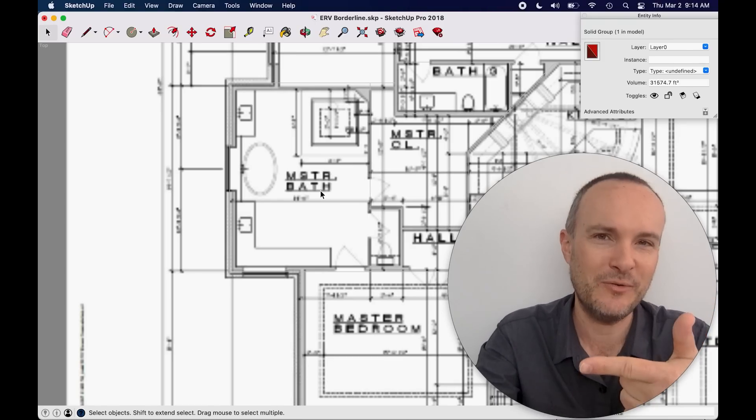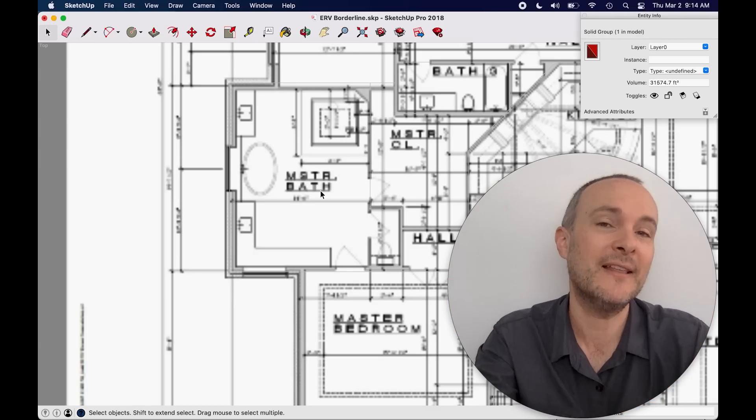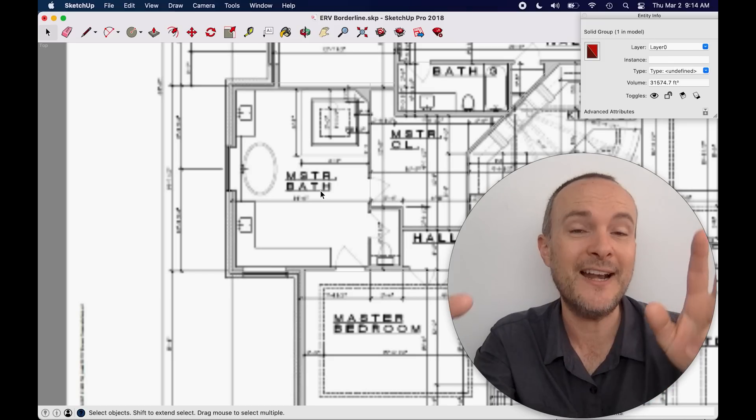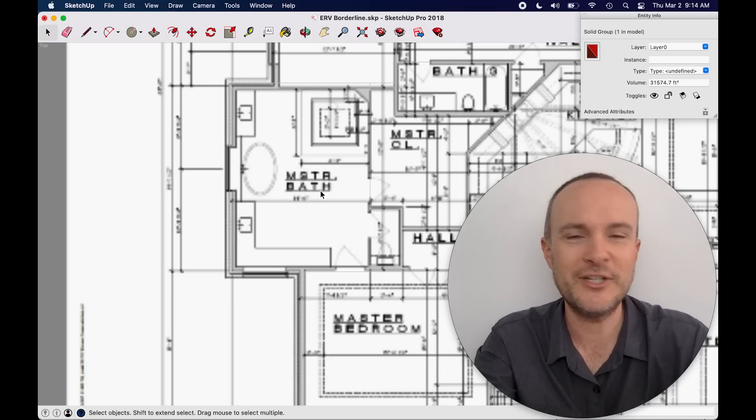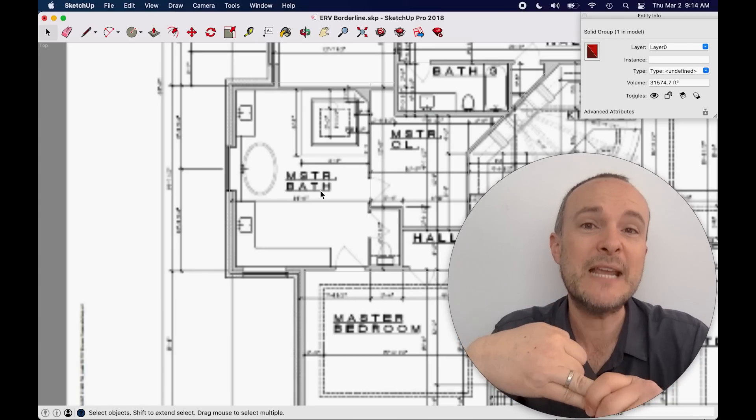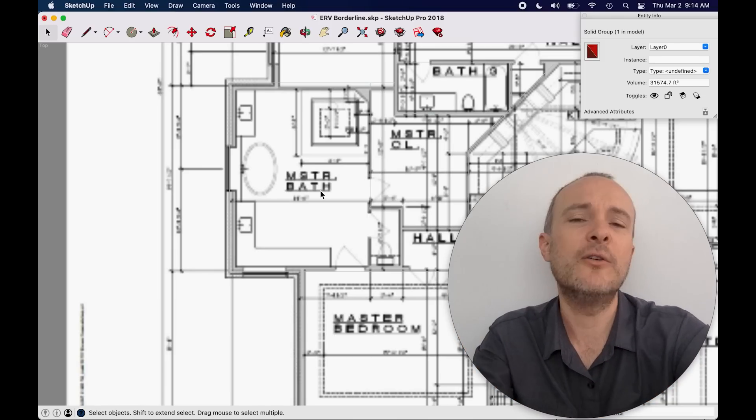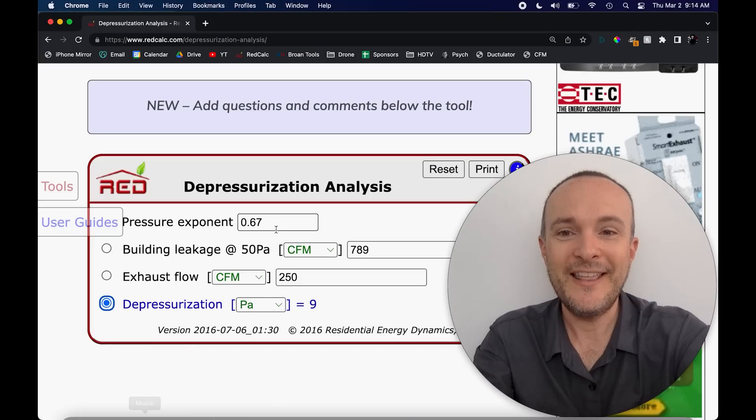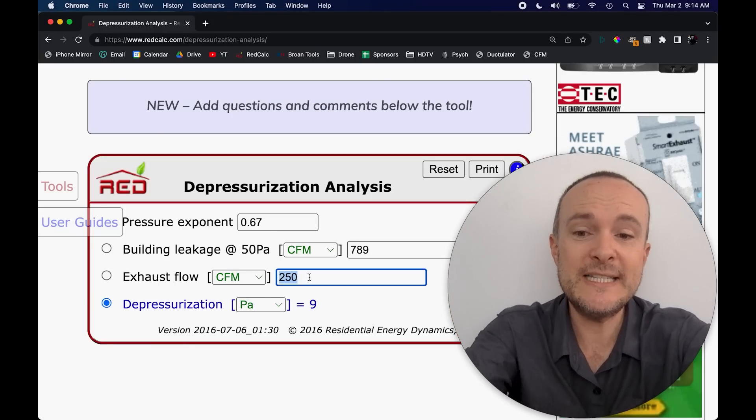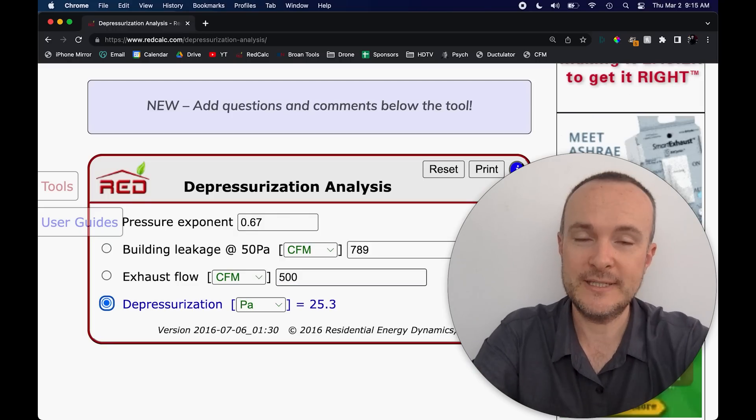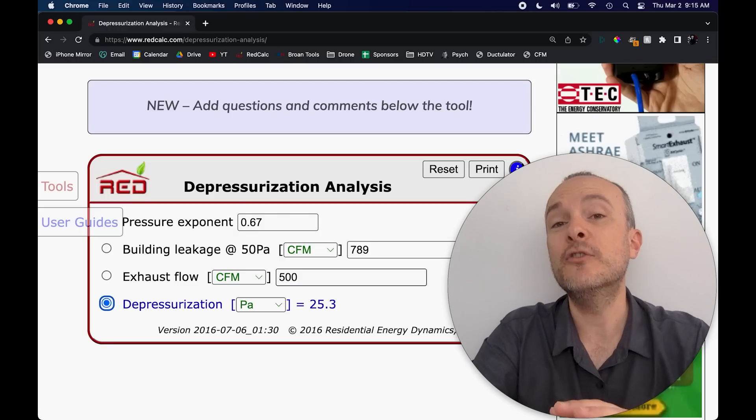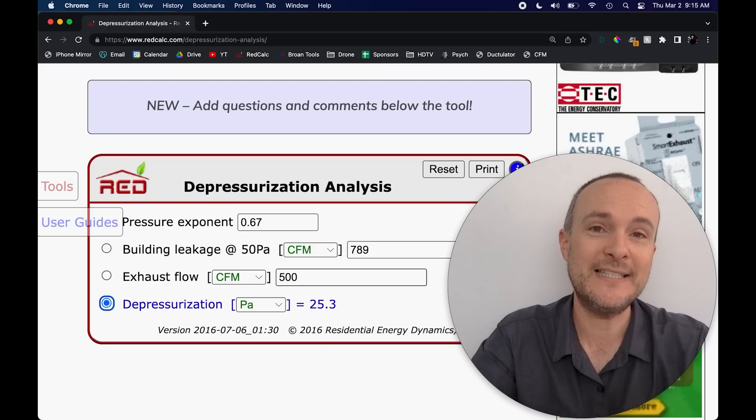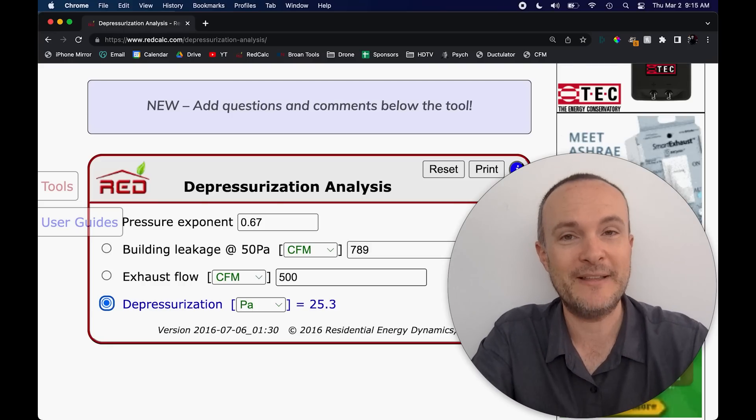Number two, it's not going to be ducted very well because it's probably installed. The box is installed by the electrician. He's going to point the duct that's supposed to go outside in a straight line, not where it's supposed to go. So they're going to have to curve that duct around. It's going to be louder. It's going to take more energy to move that air. So putting a hundred CFM in each of these, we can see now that if we did 500 CFM exhaust fans, now we're doing half a blower door test. And you can't always assume that everybody's on the same page about this. And you've got to spell it out. You can say how many CFM is the exhaust fan in that bathroom going to be and have a discussion about that.